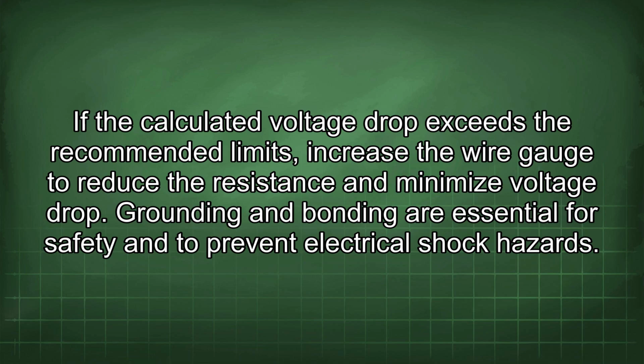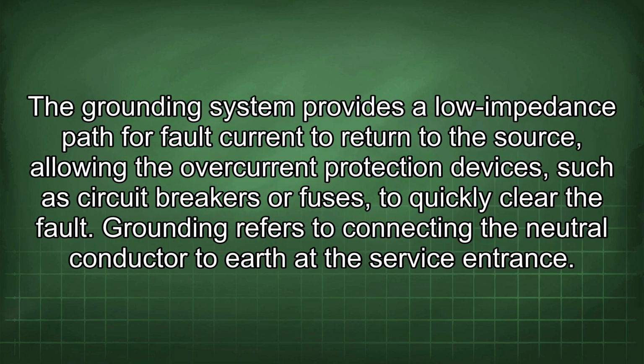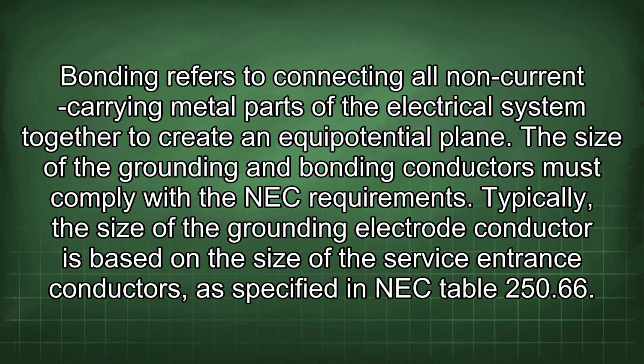Grounding and bonding are essential for safety and to prevent electrical shock hazards. The grounding system provides a low-impedance path for fault current to return to the source, allowing the overcurrent protection devices, such as circuit breakers or fuses, to quickly clear the fault. Grounding refers to connecting the neutral conductor to earth at the service entrance. Bonding refers to connecting all non-current carrying metal parts of the electrical system together to create an equipotential plane.